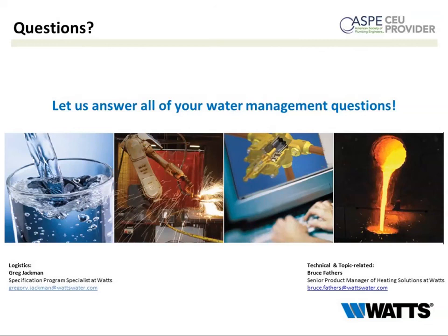Another question here: what methods can be used to mitigate Legionella from living in the supplies and local TMVs at public use fixtures where the code requires 110 degrees Fahrenheit or less hot water delivery? Right. So there are other methods for Legionella mitigation. Now, if you can't do a flush, a flush is just for a very specific amount of time. If you're not allowed to flush, obviously there's other mitigation options: chlorination, copper, silver. There are also basic design things like making sure there are no dead legs, continuously running water, right?